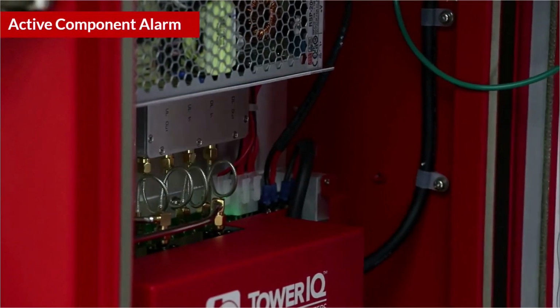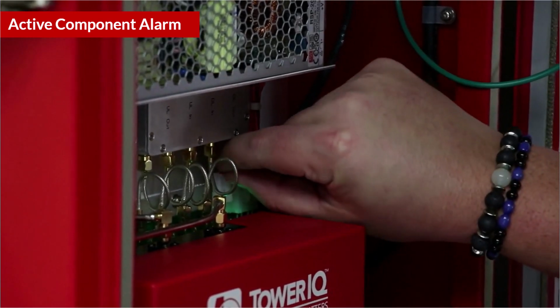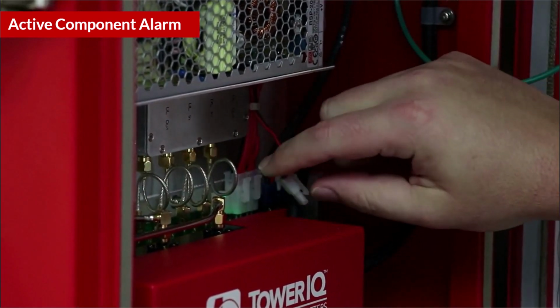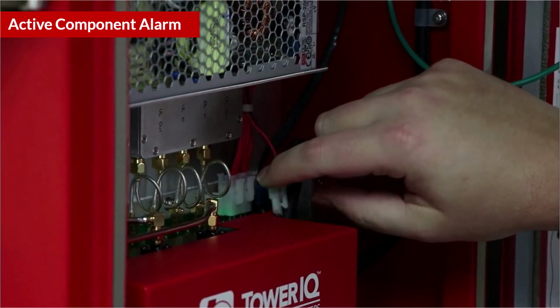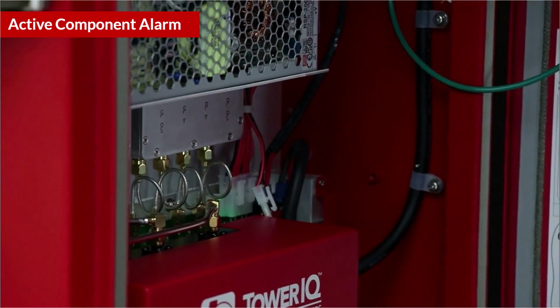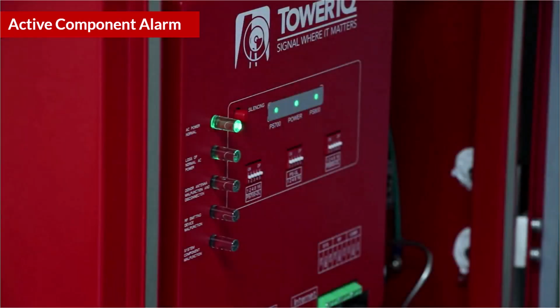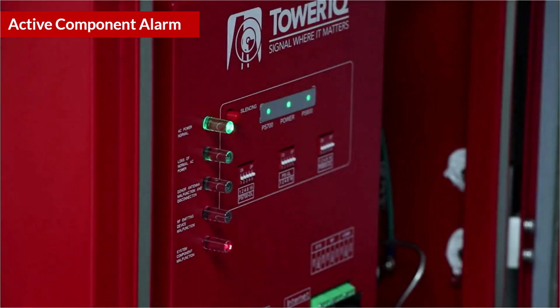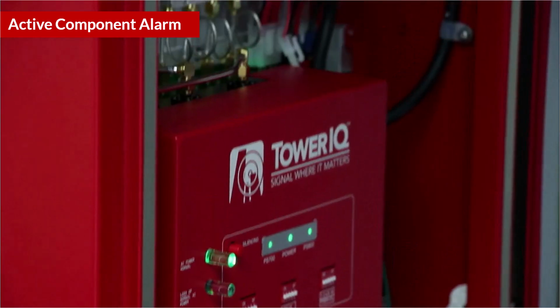The active component alarm, or system component malfunction alarm, checks the active components for integrity and activates when overpowering occurs, since we obviously do not want to overpower the PC board and potentially damage the BDA. We can demonstrate the alarm is functioning properly by eliminating power to the PC board. On the top of the BDA, simply disconnect the power line to the PC board seen here. This alarm will take 3 to 5 minutes to activate.